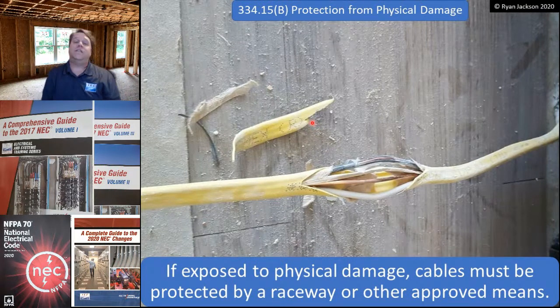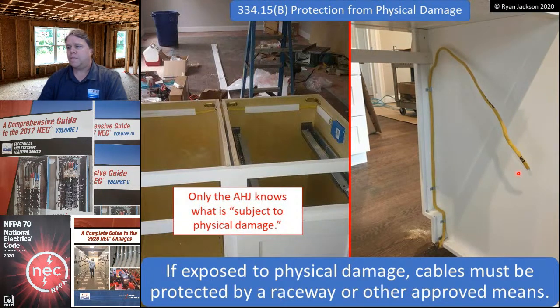I don't know how to define physical damage. You can't define physical damage, but you know it when you see it. So a lot of people say, well, what's physical damage? I don't know. You can't possibly define it. Somebody has to make the choice. Somebody has to make the determination of what physical damage is. So, do you need to put these sleeves inside of the cabinetry? I don't know. That's up to your authority having jurisdiction. Is this underneath this cabinet subject to physical damage? I don't know. That, again, you'd have to ask your authority having jurisdiction.